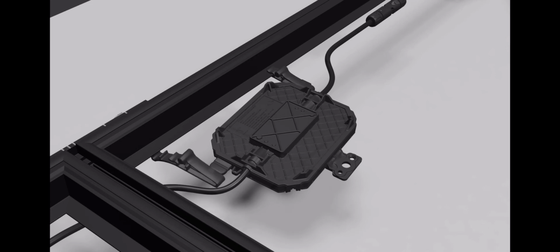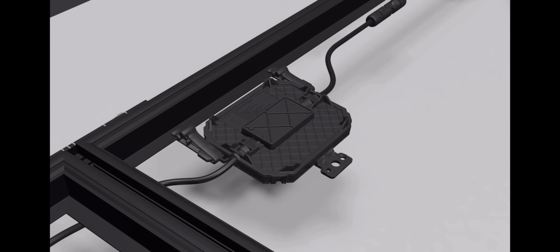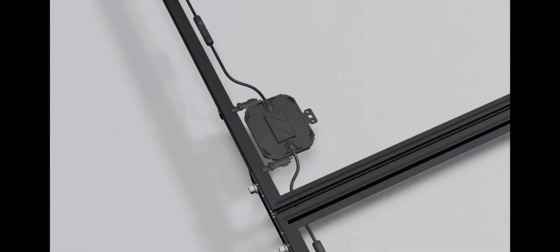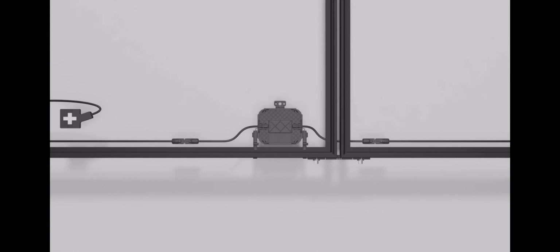Place an open home run clip onto the tab, snap the clip into the module frame, and finally, lock the clip onto the tab. Now that the MCI has been securely mounted, loose wiring must be managed. Install multiple clips to the module frame to secure the wires, including module leads and MCI leads. Please remember to follow all standards and guidelines for proper wire management.